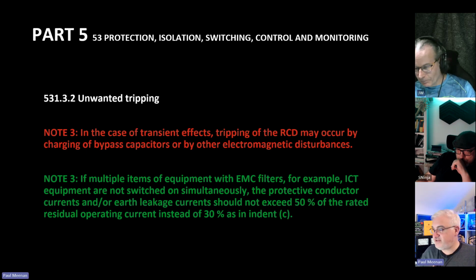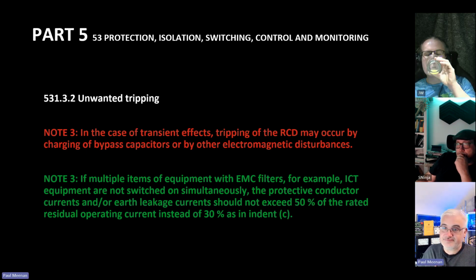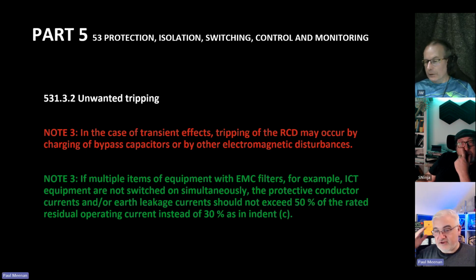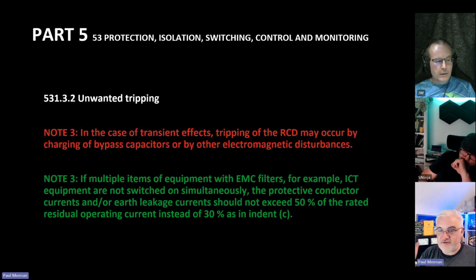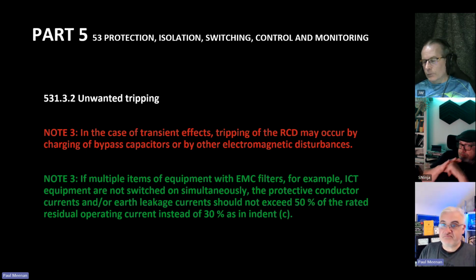But again, John, this is a regulation not many actual people follow. People don't exactly go around and design the fixed equipment and the leakage. They don't bother because, if you remember, it's one of them technical reports that we covered in a past podcast where there was a formula: number of equipment times 0.75 would give you the leakage. You can then go to the product standards and work out what your leakage was. This is now saying, rather than being 30% or 9 milliamps, you can now have 50%, so you're at 15 milliamps. So you're right, some devices may be that sensitive. It will be quite interesting.